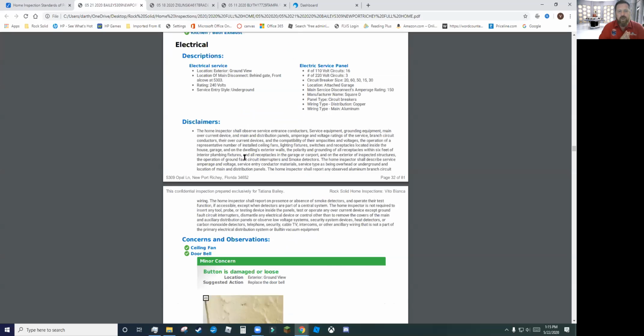On the electrical, as you can see, we have the descriptions already in place. The electrical service was behind a gate at a front alcove. This was a weird shaped property, but I described where it was. It was 240 volts, came in underground. The electrical service panel had sixteen 110-volt circuits, three 220-volt circuits. I described the circuit breaker size and location - it was a 150 amp rating at the disconnect. It was a Square D panel with circuit breakers instead of fuses, copper distribution, aluminum on the main. Aluminum on the main is normal and okay.